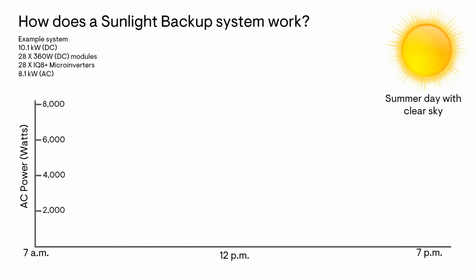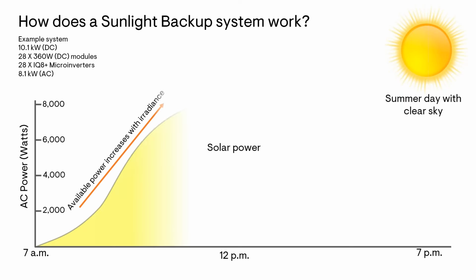So I've got a couple little animations here to illustrate how a sunlight backup system works in the real world. This example is with a 10 kilowatt DC system, which is an 8 kilowatt AC rating based on the microinverter power output. The amount of available power depends on the irradiance, or intensity of the sunshine. On a sunny day with clear skies, the available power at sunrise will be low. It'll gradually increase throughout the day until midday, and then it starts to gradually decline until the sun sets.